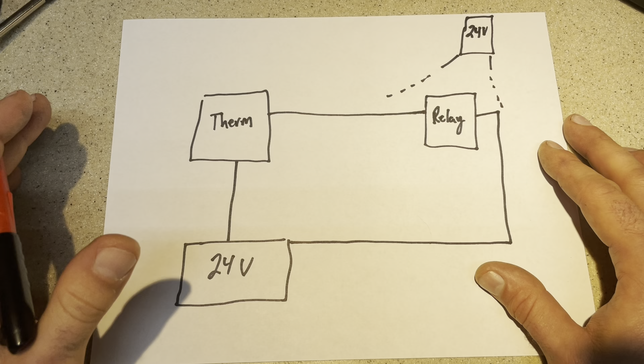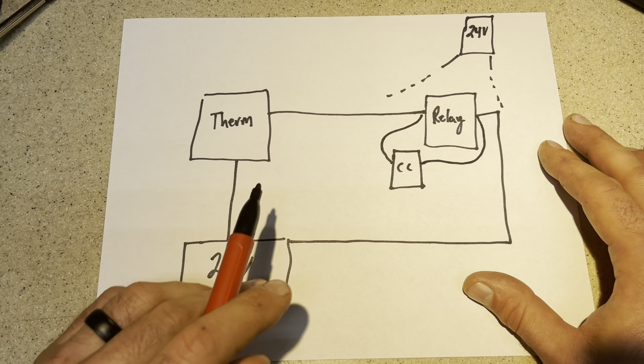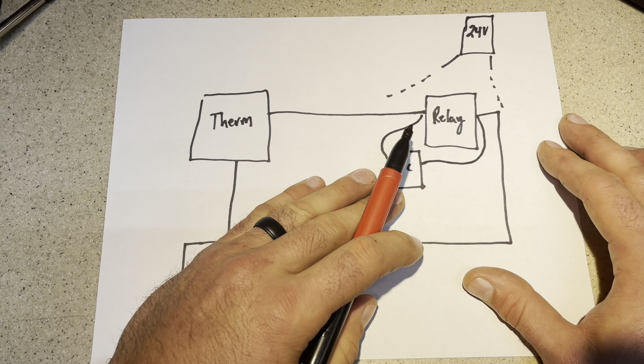Well, not so fast. To be extra thorough, you go get a contactor, a sequencer, any kind of little 24 volt load out of your van. So I'll draw in a contactor here. You take jumpers and connect them up to the wire, and the contactor doesn't activate. So you measured 24 volts open circuit, but then you hook up a load and this known good contactor still doesn't activate. So what's the problem?